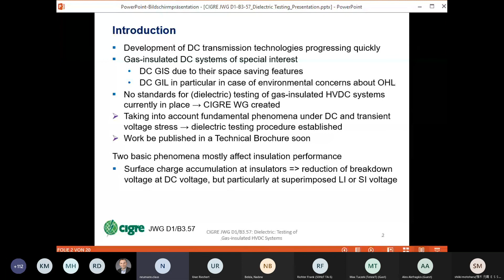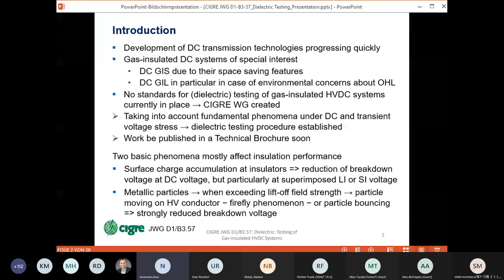What are the basic phenomena which mostly affect the insulation performance of gas-insulated HVDC systems? First, we have to mention surface charge accumulation at the insulators that will reduce the breakdown voltage at DC voltage, but in particular at superimposed lightning or switching voltage. And the other phenomenon is the metallic particles. We have to take into account that when the lift-off field strength is exceeded, the particle starts to move onto the high voltage conductor, which causes this firefly phenomenon, or the particles are bouncing between the conductor and the enclosure, and that strongly reduces the breakdown voltage.